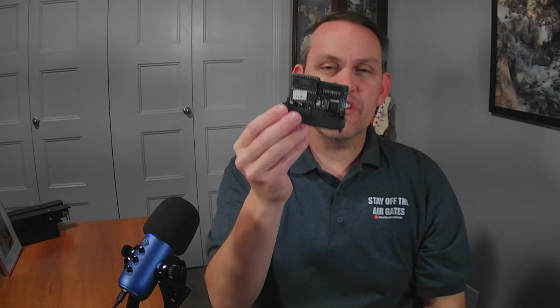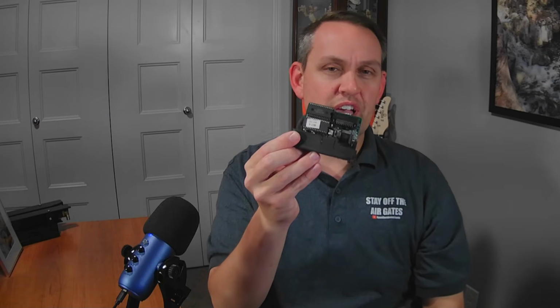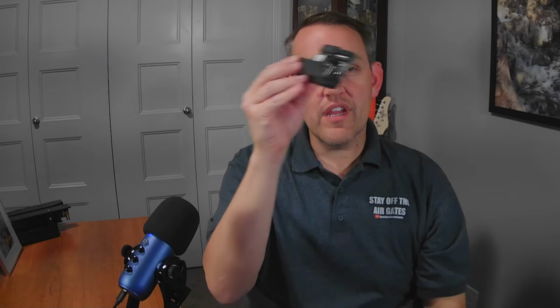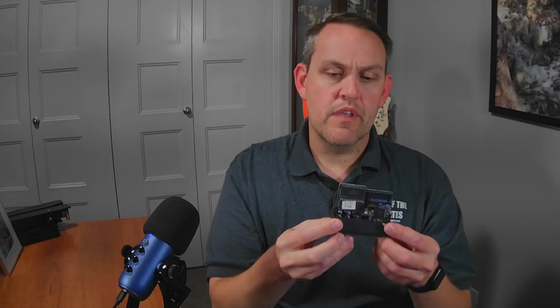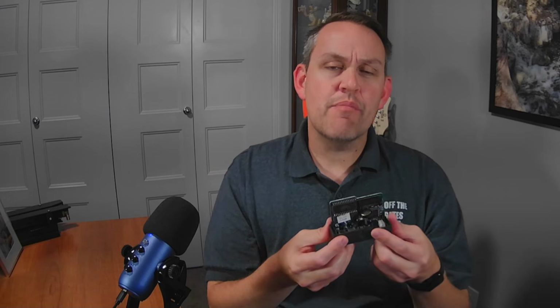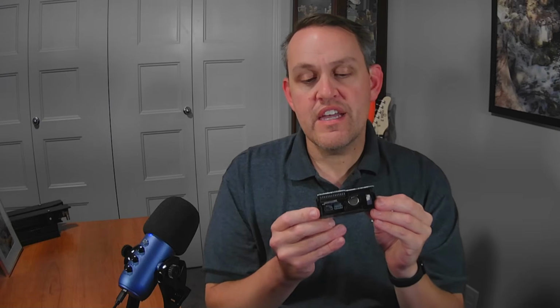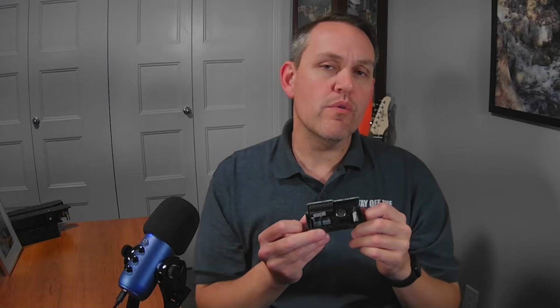The PLC operation is divided into 4 steps: read, execute, communicate, and write. How it moves from step to step every cycle is called a scan. The scan is the component that runs internally inside the processor, and depending on the processor, it could run anywhere from a couple of times per second to thousands of times per second. So let's explain the scan cycle really quick.